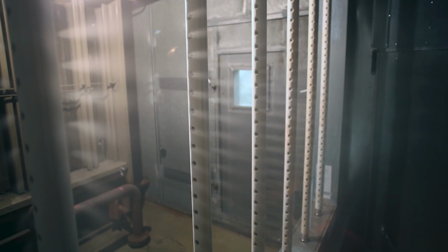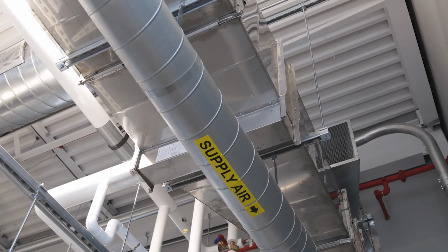When we start thinking about, okay, we have our steam source, how would you then distribute the steam within an airstream? And maybe what are some of the dry steam options that a person could consider? So in general, it depends on what your goals are. If your goals are to humidify an entire building, the fewest pieces of equipment is the most economical solution. In that case, potentially going into an air handler if it is serving a lot of the different spaces. And so putting that steam directly into the air handler or in the discharge duct out of it would be practical.